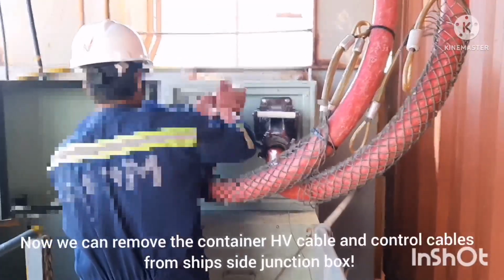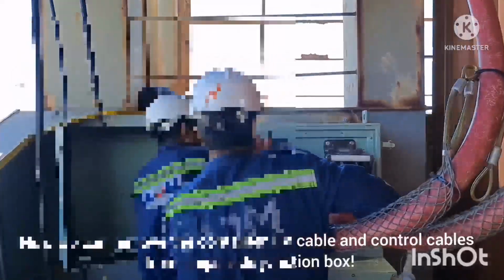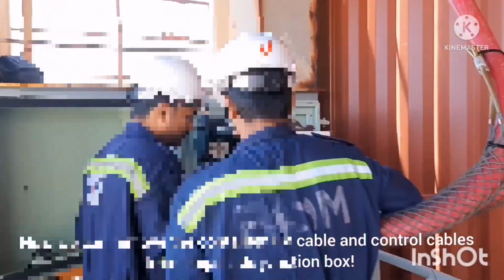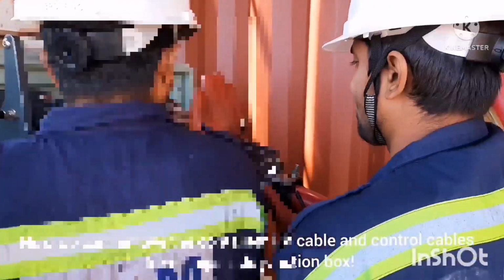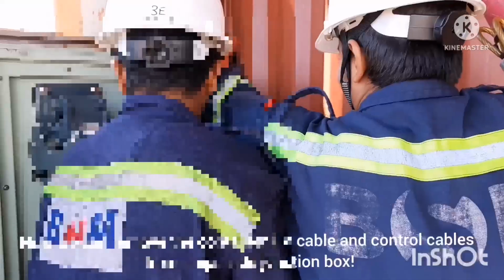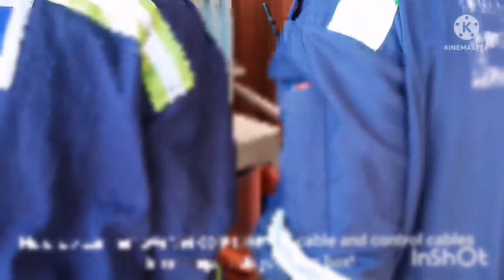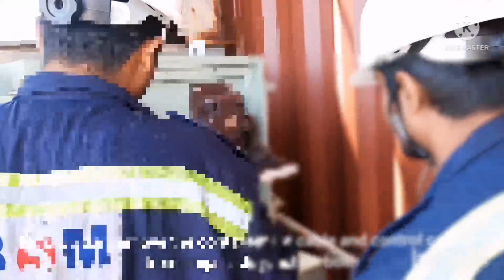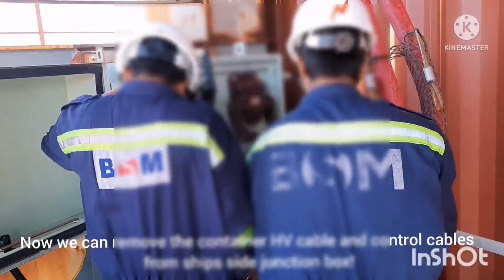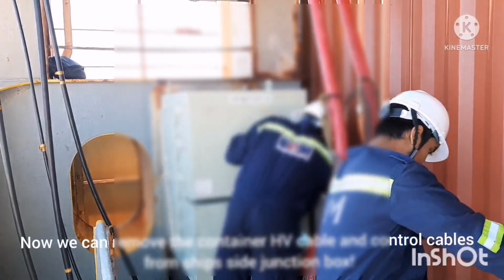Now we are removing the high voltage cable and control cables from the ship side junction box. Again, while removing we need to hold it at a 45-degree angle. Just lift the safety lever and pull the cable out, and the cable is out. Always be very safe while doing that. Once the cable is removed, lock it, close the socket box cover and secure it.